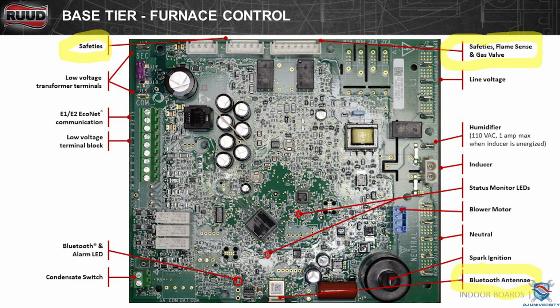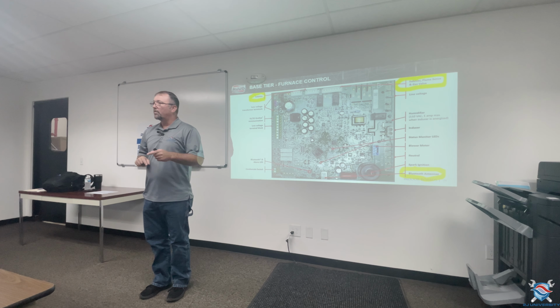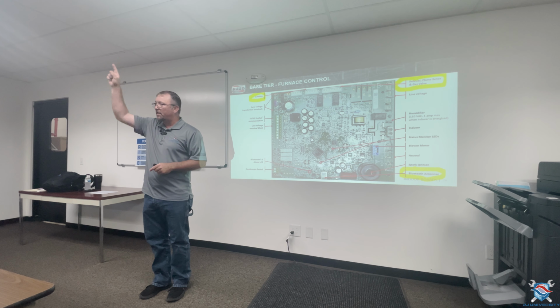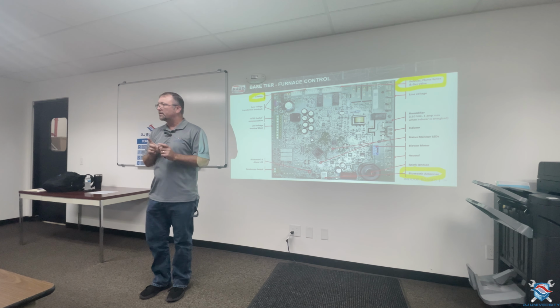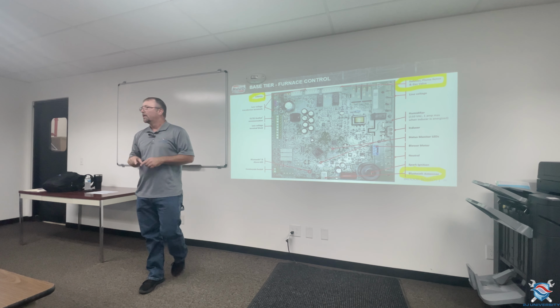So in the past, you've always had furnaces that wire in series back to the gas valve, and then you'll get a code off of any of those things opening back to the gas valve. Typically all safeties, right? Well, what they've done with this new board is everything's home run. So it goes out and comes right back to the board. Your gas valve, low and high fire, same way. Goes out, comes right back to the board. So nothing's wired in series now.